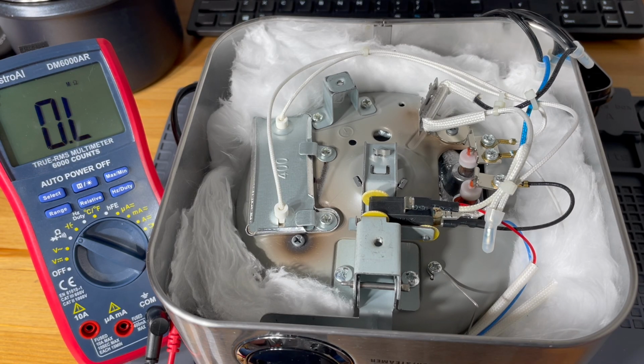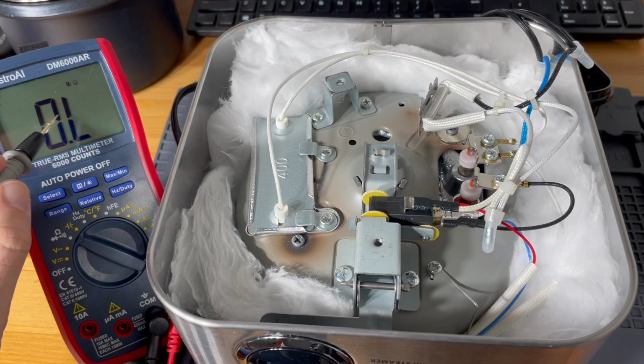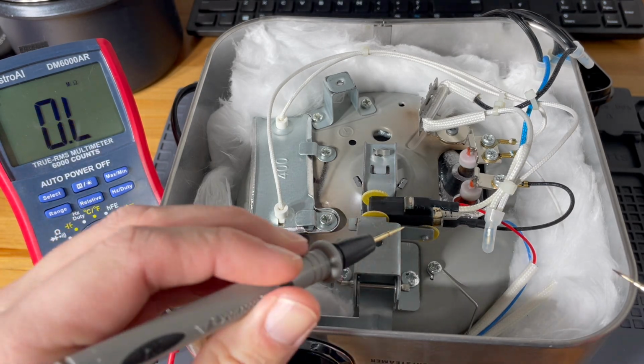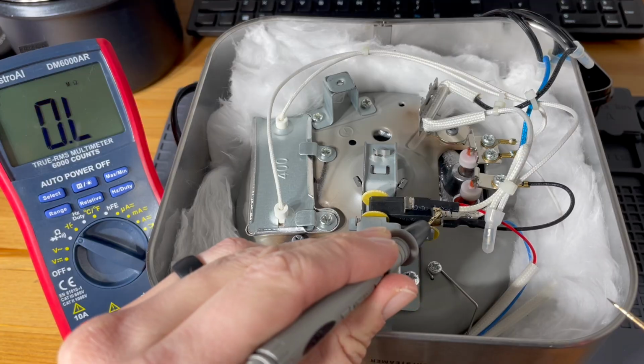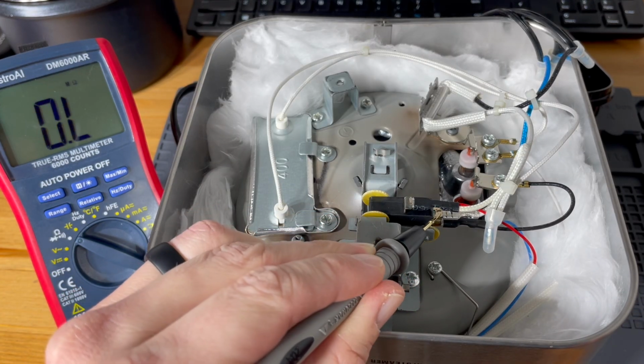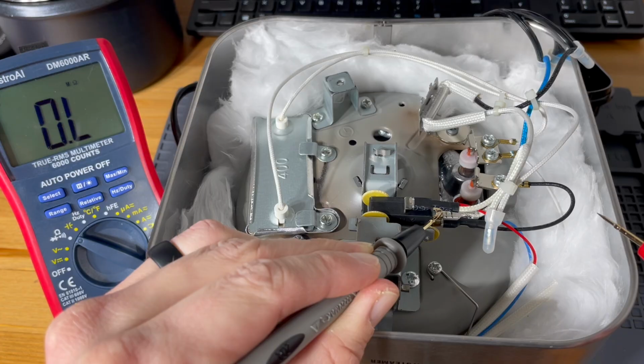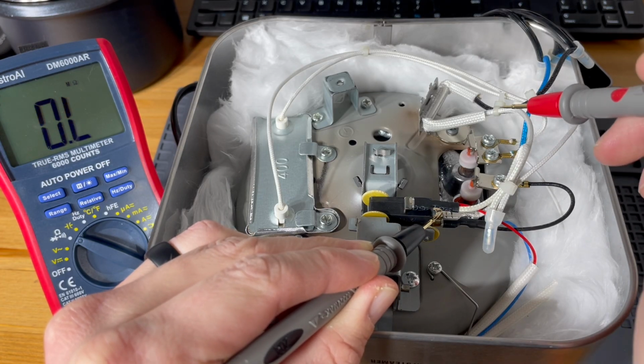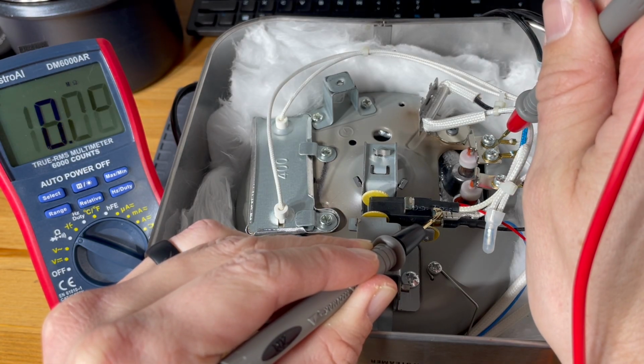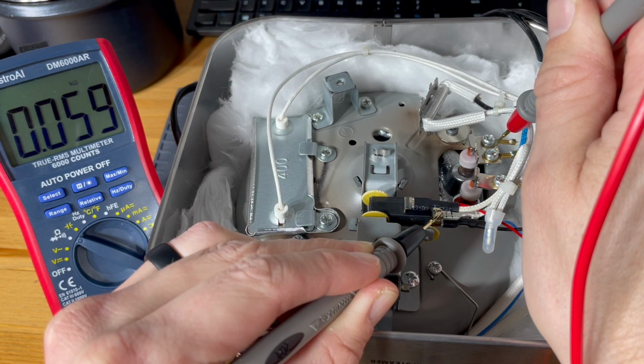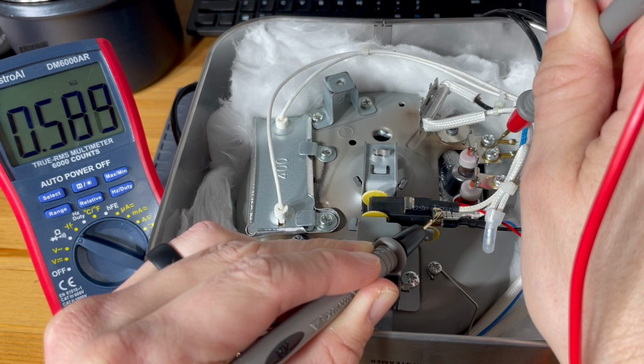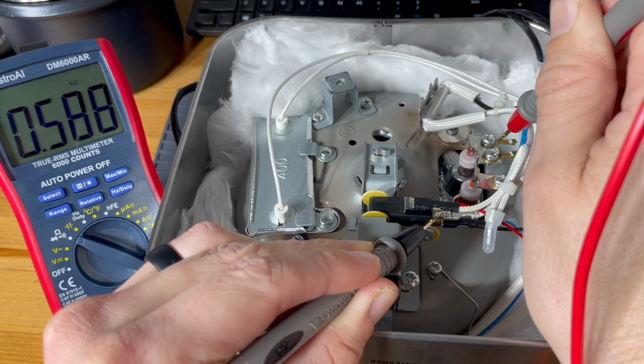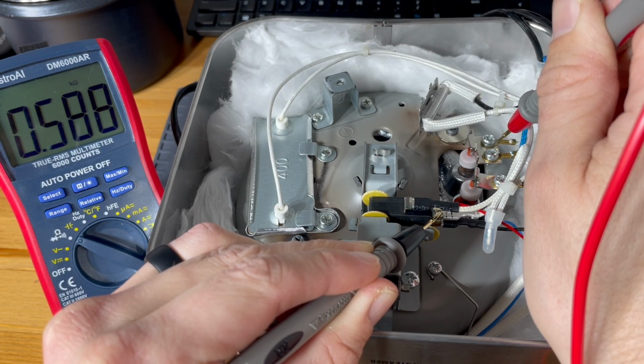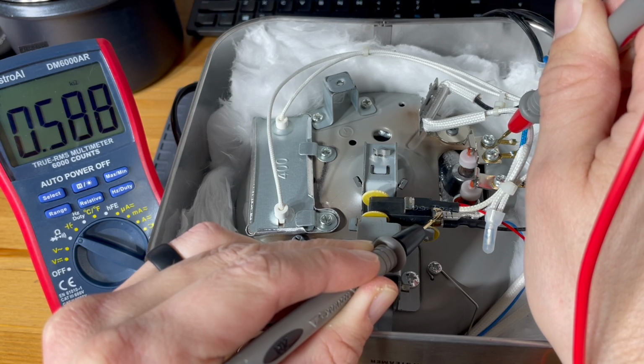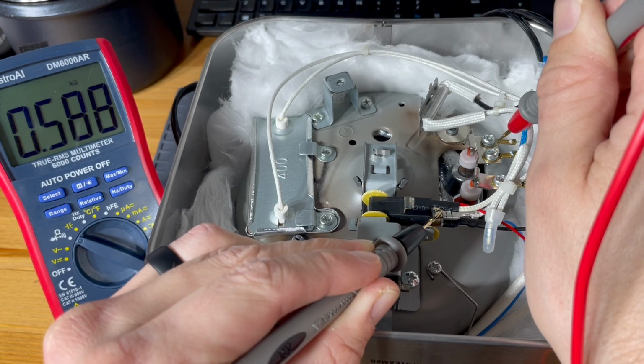Okay, so let's put that to the test. I've got the meter set to resistance, and if I put one probe on where the power goes into the warm circuit, and the other probe just anywhere on the neutral that goes back to the wall, I'm seeing 0.588 kiloohms, or 588 ohms. Okay, so we'll keep that number in mind.